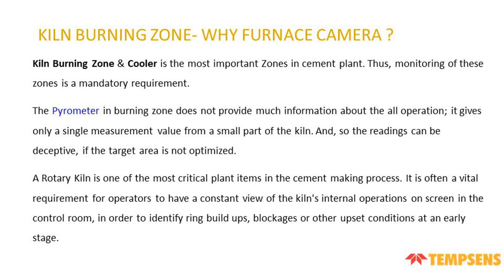The pyrometer in the burning zone does not provide much information about the overall operation. It gives only a single measurement value from a small part of the kiln, so the reading can be deceptive if the target area is not optimized. The rotary kiln is one of the most critical plant items in the cement making process. It is often a vital requirement of operators to have a constant view of kiln internal operation on the screen in the control room in order to identify ring buildups, blockages or other upset conditions at an earlier stage.